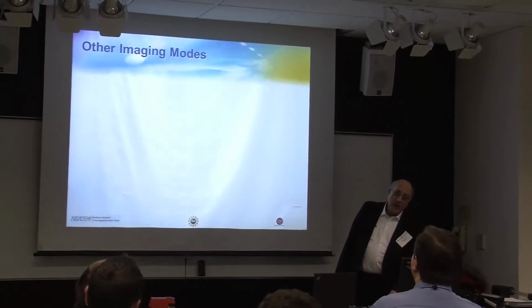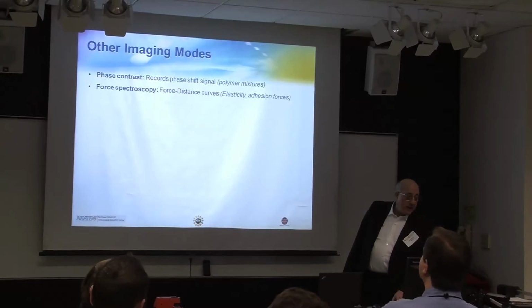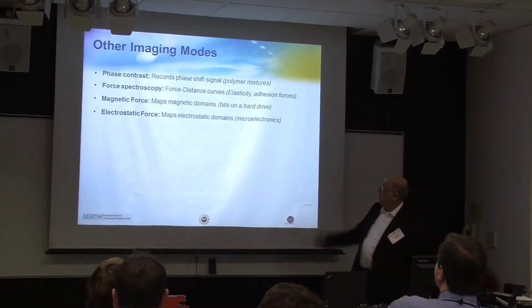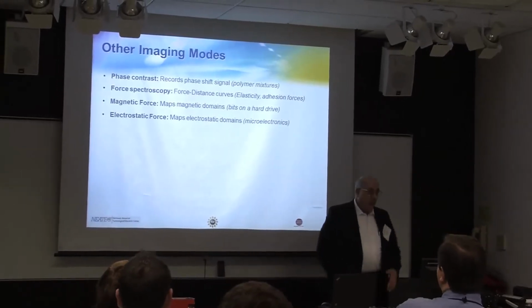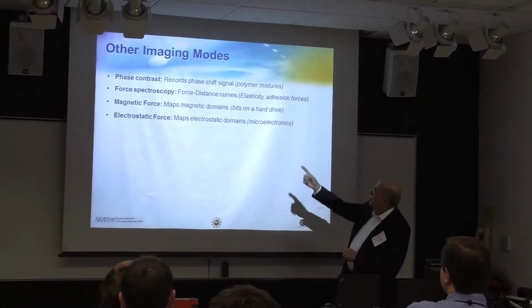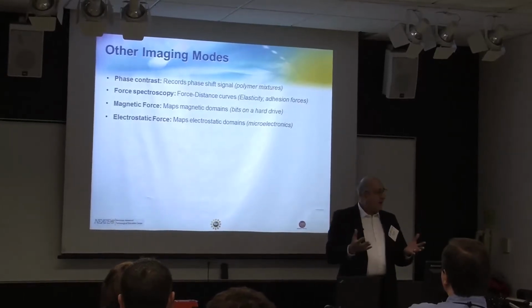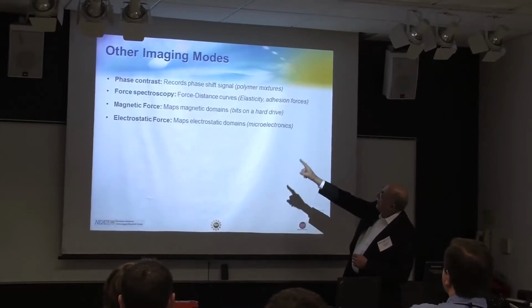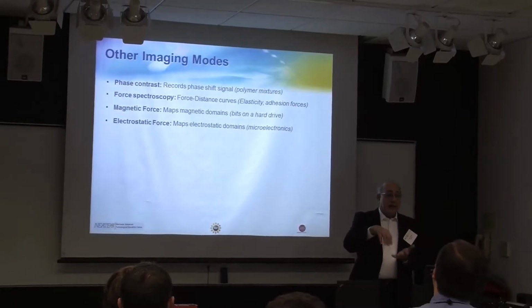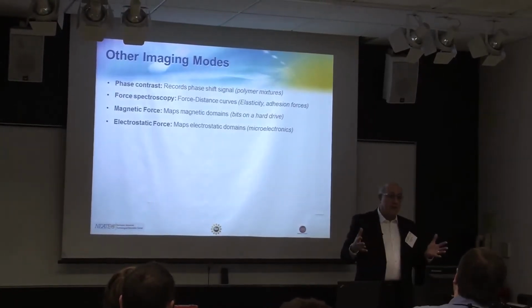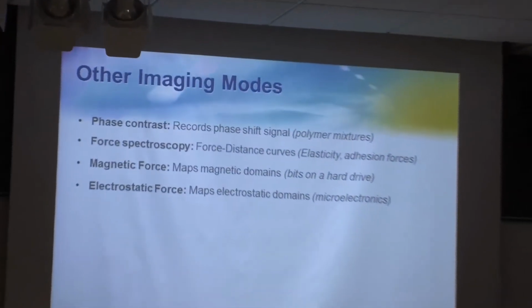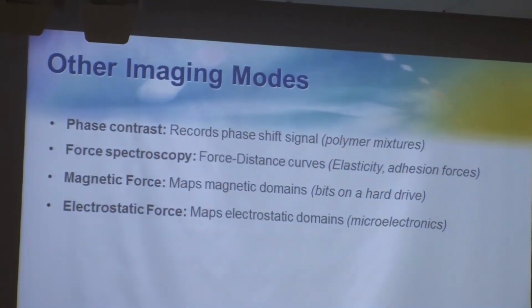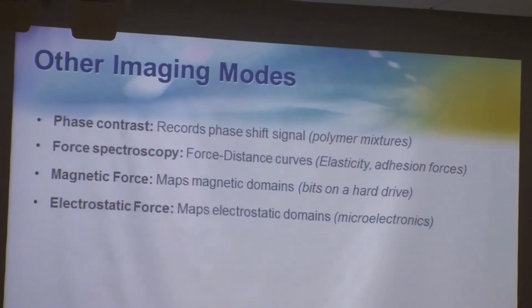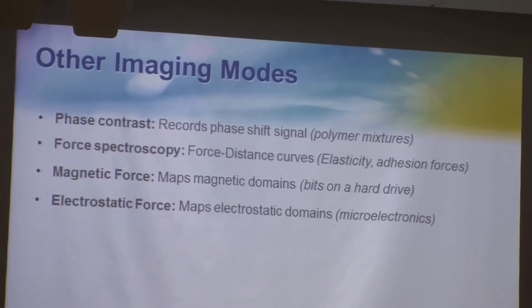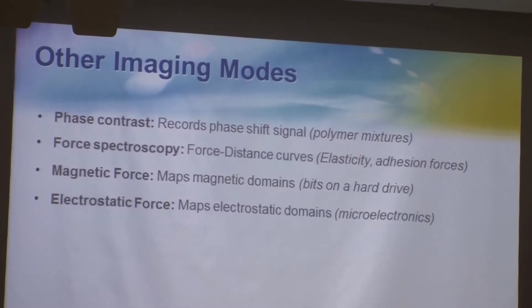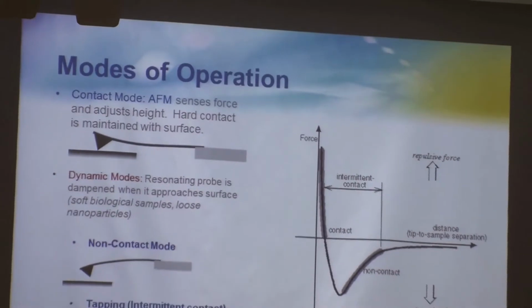There are other ways to operate this. These are the three important ones. Sometimes you don't want to do only a contour or a picture. For example, you may want to find out about the composition of the sample, and we use the phase. This device can measure the phase of the force, and the phase will tell you something about the composition of the sample. There are other types of measurement depending on what you want to do. For example, for microelectronics we normally use a mode called electrostatic force, and we can measure the p-n junction, the depth, and so forth. There are many ways, but basically these are the three most important, or two.